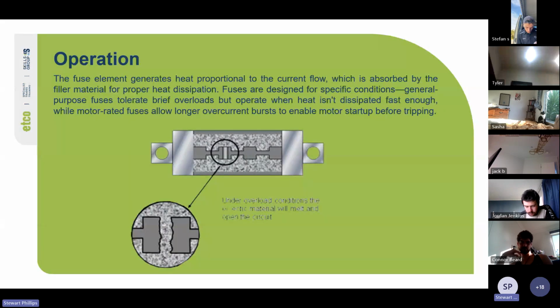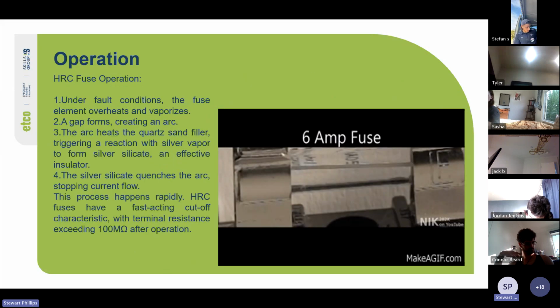So operation: the fuse element generates heat proportional to the current flow, which is absorbed by the filler material for proper heat dissipation. Fuses are designed for specific conditions. General purpose fuses tolerate brief overloads but operate when heat isn't dissipated fast enough, while motor rated fuses allow longer overcurrent bursts to enable motor startup before tripping. Under overload conditions, the fuse element will melt and open the circuit. This is the HRC fuse operation.